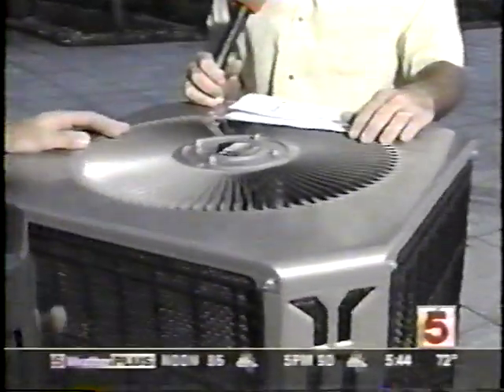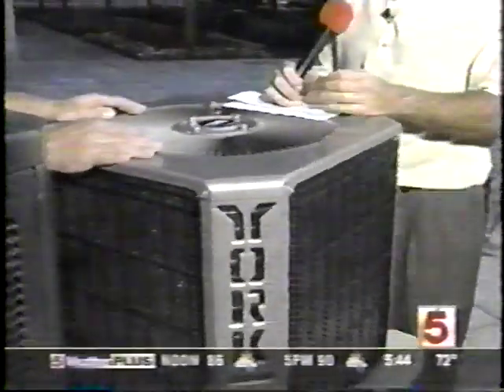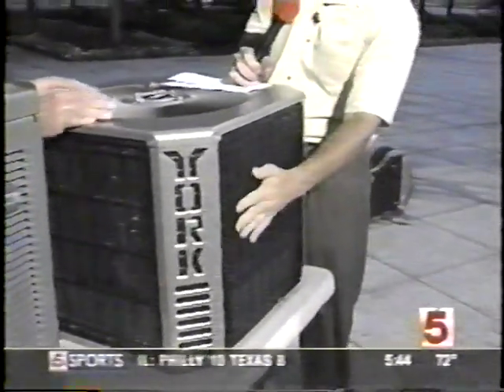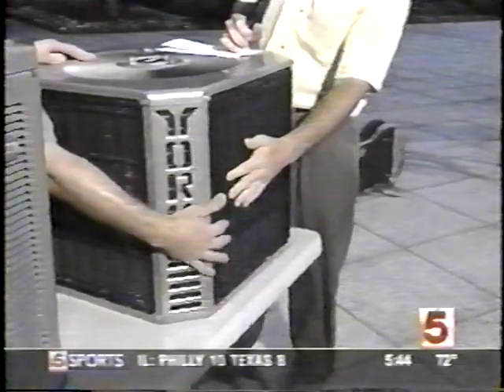Make sure the unit is clear of debris, grass clippings, shrubs, etc. When you're saying the unit, you're talking about some of the coils on the front, is that right? The coil area itself is here. You want to be at least 12 to 16 inches away from the unit for proper operation. Because a lot of people probably like to plant bushes and shrubs right up against it, but you say that's not a good thing to do. No, not at all. You want to have, like I said, 12 to 16 inches of circumference around the unit free of debris and obstruction.